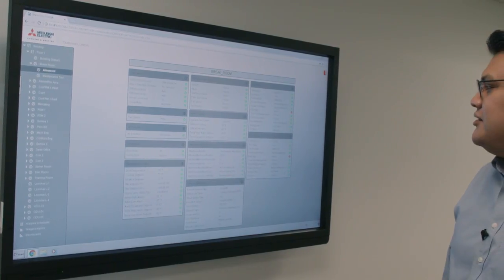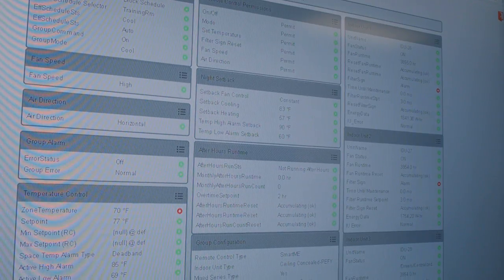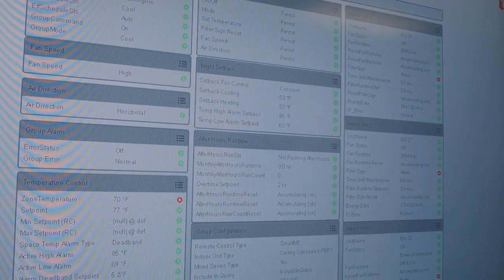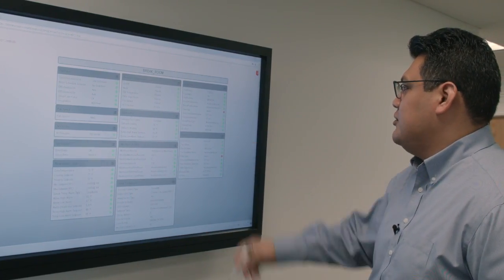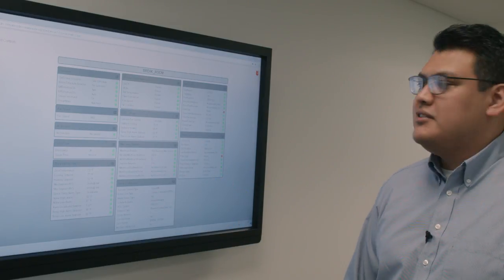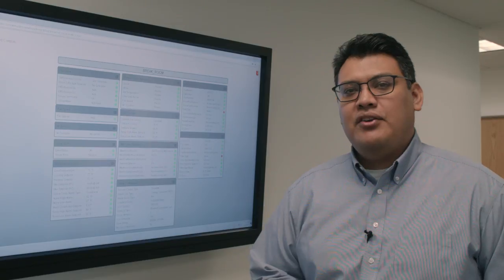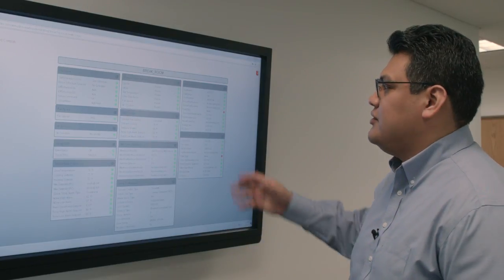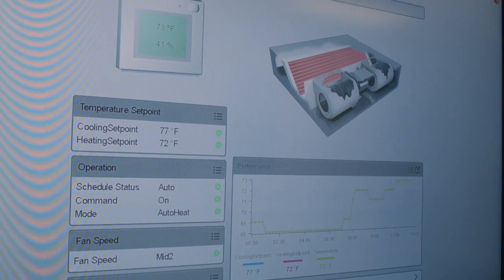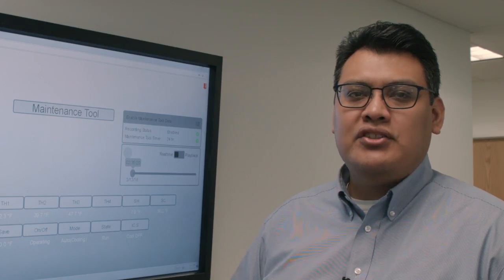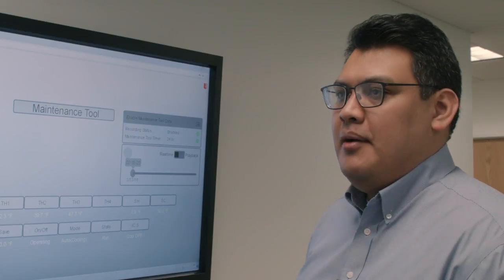There's an advanced tab where you can see the setback functions for when nobody's in the space. In this scenario, in heating mode it sets back to 65 degrees and in cooling mode it sets back to 78 degrees. Those are some of the great functions you can use to see what the system is doing and how it's performing — great data you can share with your maintenance contractor to service and maintain this equipment.